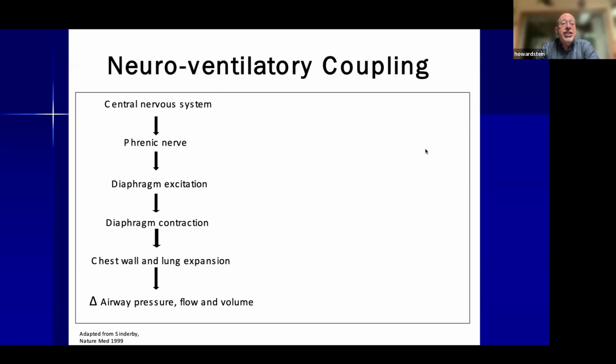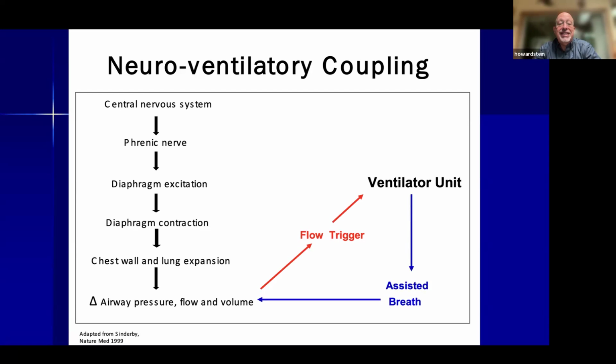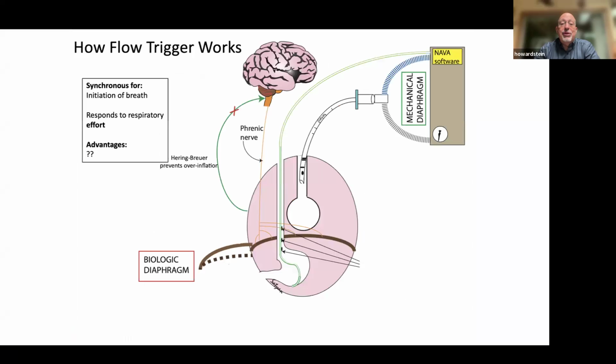So, quick review. The signal starts in the central nervous system, comes down the phrenic nerve, and the diaphragm contracts. The chest wall and lung expand, and as you take this breath in, you get this change of flow and volume. That sends a signal to the ventilator, and that's the flow trigger that tells the ventilator to give an assisted breath. With neurally triggered ventilation, we're picking up the signal much earlier. The neural trigger starts when the diaphragm gets excited, and then the ventilator will give the assisted breath. To look at it again, the signal comes down the phrenic nerve, excites the diaphragm, it contracts, then air has to move. Once that air moves, it tells the ventilator that the valve is open, and the ventilator then delivers a breath to the patient.